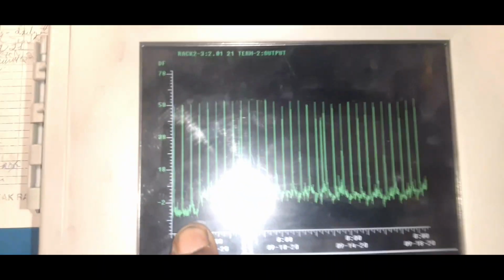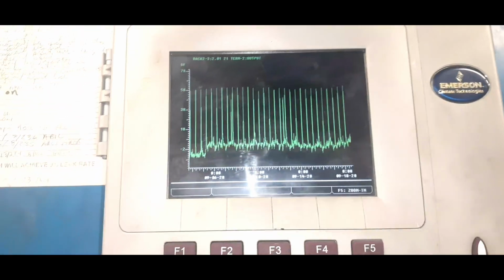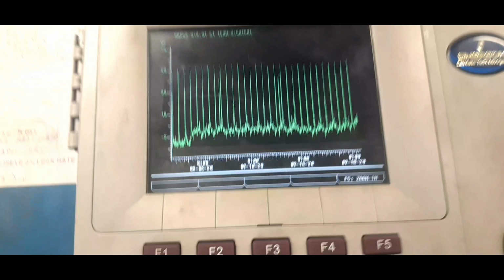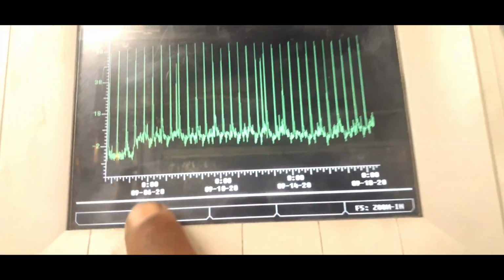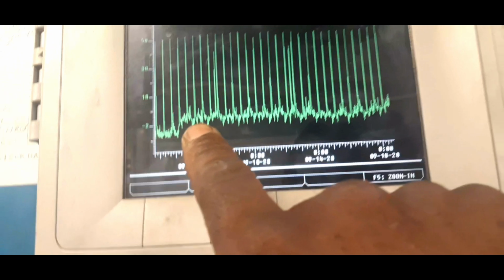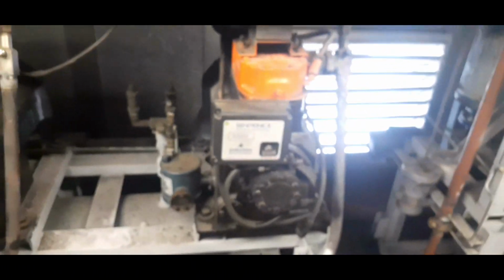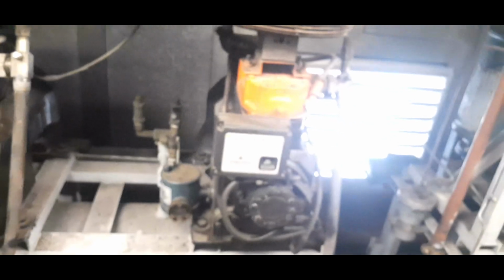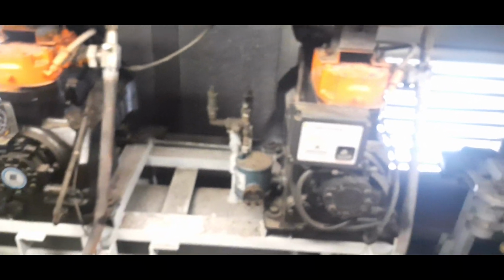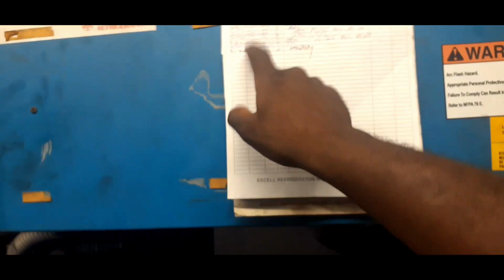So ever since the 6th, we've been running a high suction. Look at that. So you see the way that trend is starting to trend higher. That's probably around the time when that compressor probably went off, and we haven't been out since. I haven't checked the call history or anything like that, but that's around the time. That was the 9th. So somebody didn't log it here. But as you can see, we definitely not coming down.